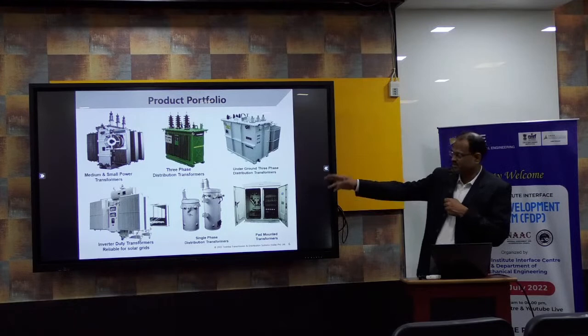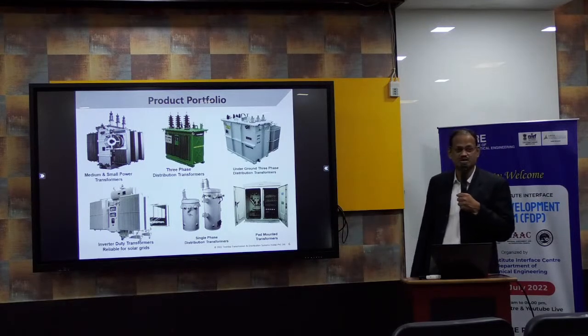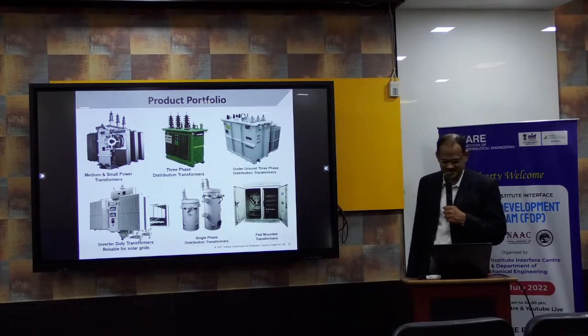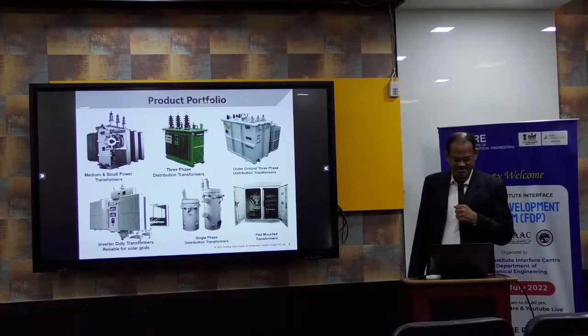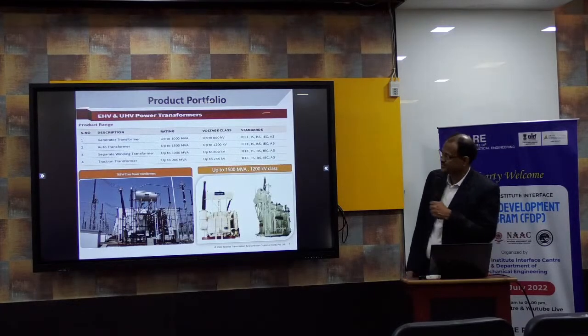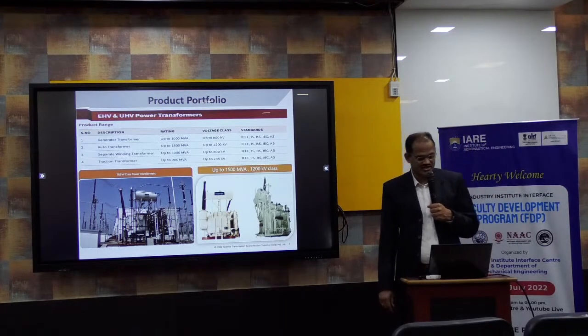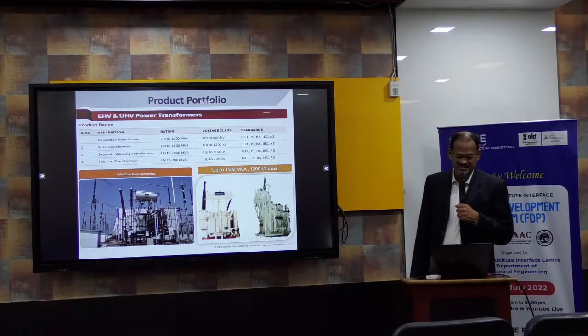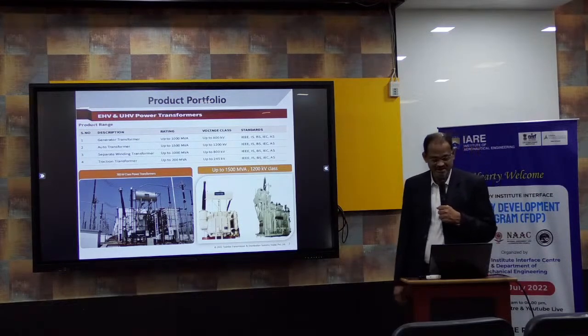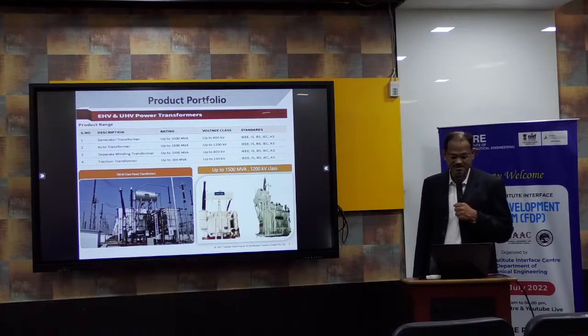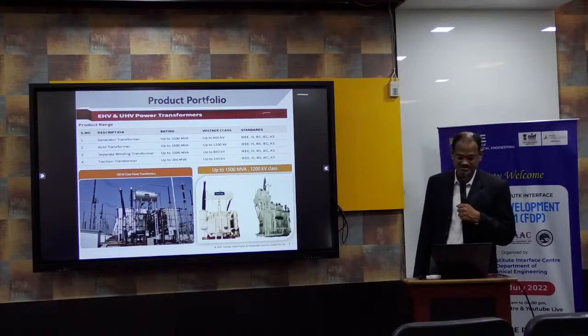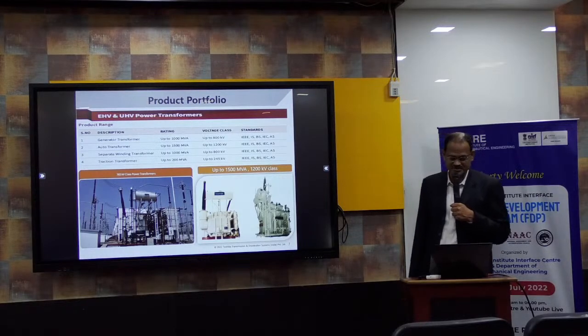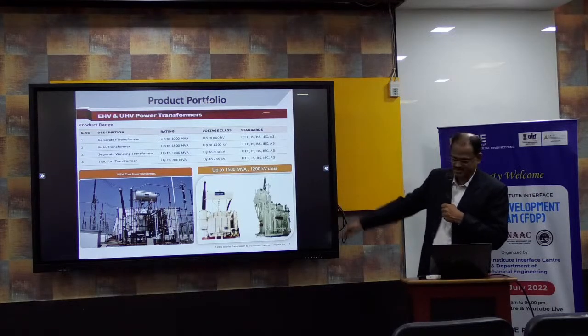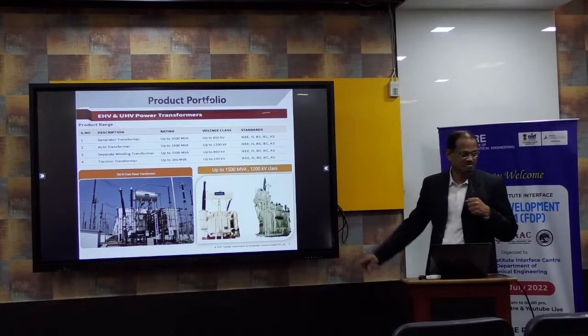Remaining all are single phase pole mounted, where poles are installed, and that is the inverter duty transformer. For all solar panels and solar power generators, we require an inverter transformer to generate and transport the power from the solar plant. These are the varieties of distribution transformer. Going to the next, EHV, extra high voltage, and ultra high voltage power transformers. There are generator transformers up to 1000 MVA, up to 800 kV class, the auto transformer up to 1500 MVA, 400 kV class, separate winding transformer 1000 MVA, up to 800 kV class, traction transformer 200 MVA, up to 245 kV. This is some of the installation photographs, and in the other photographs you can imagine how a power transformer looks.